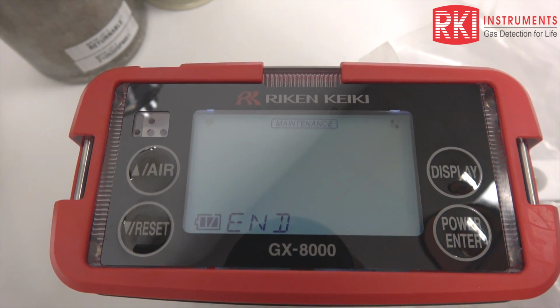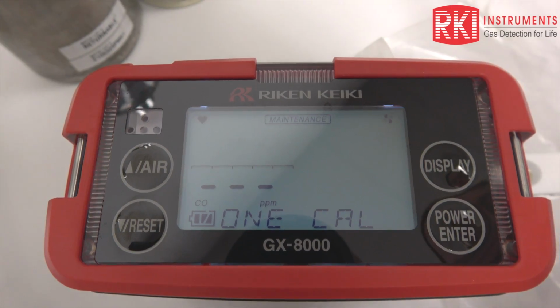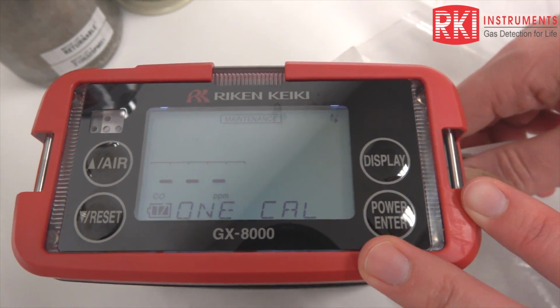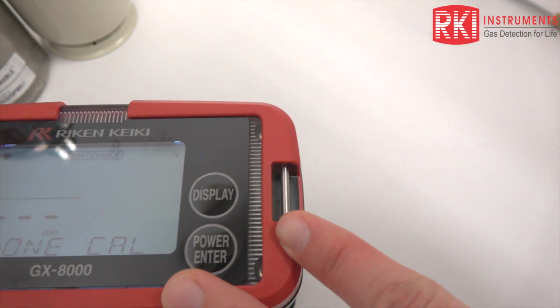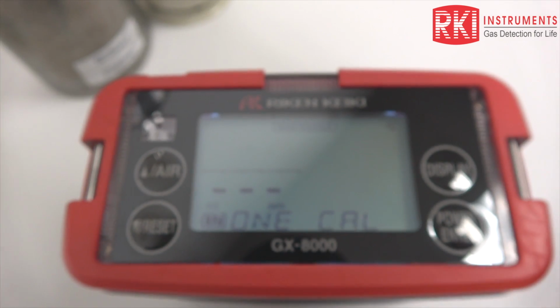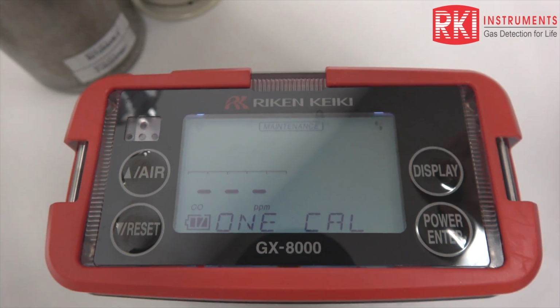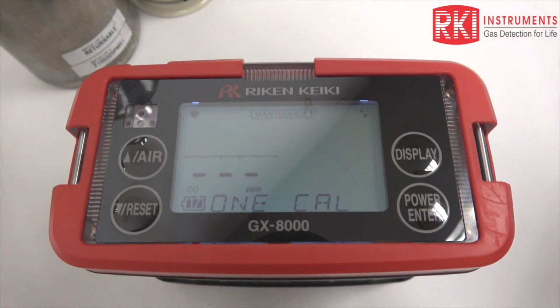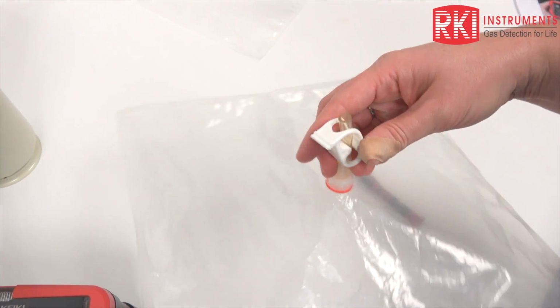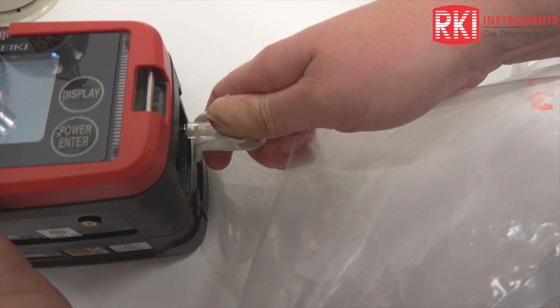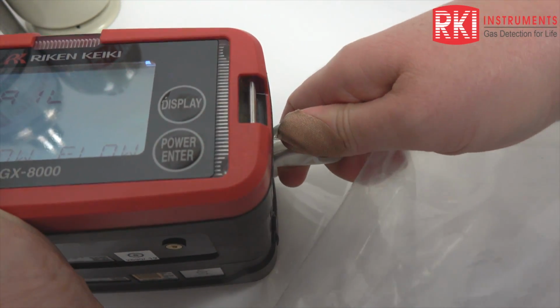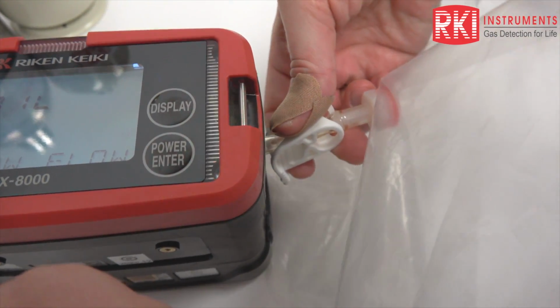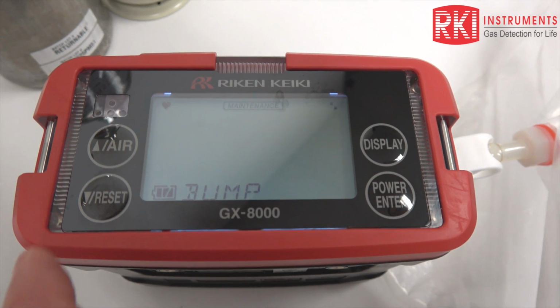Okay. So the last sensor I have left to do is now my volume combustible sensor. And what I'm going to use for that is 50% volume methane, because that's what we have in the building. Again, you need to use whatever combustible gas is appropriate for your application. So this is my gas bag of 50% methane. I'm going to hook it up. It's going to go into flow fail. I'm going to release my clamp, press reset.